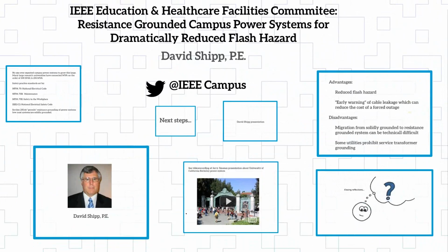So what you're telling me, they've actually started to do this where they're making it mandatory on the 480-volt hospital systems, at least in the emergency rooms. Is that what you're confirming to me? That's what I heard at the IEEE conference last week, that it's now a state code, California state code, that healthcare must be high resistance grounded.